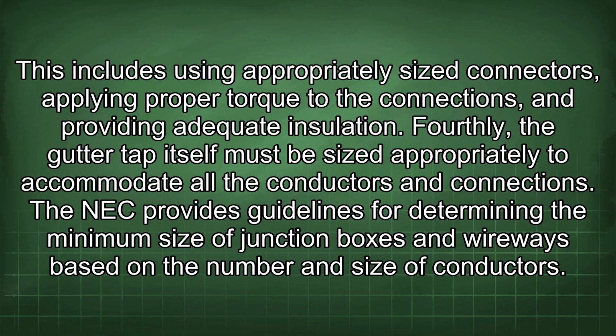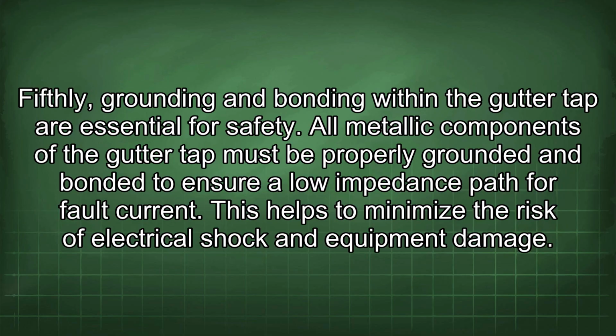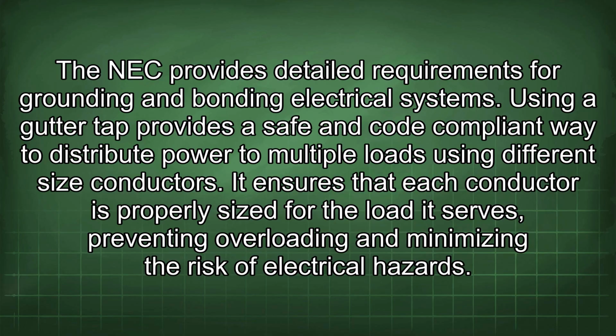Fourthly, the gutter tap itself must be sized appropriately to accommodate all the conductors and connections. The NEC provides guidelines for determining the minimum size of junction boxes and wireways based on the number and size of conductors. Fifthly, grounding and bonding within the gutter tap are essential for safety. All metallic components of the gutter tap must be properly grounded and bonded to ensure a low impedance path for fault current. This helps to minimize the risk of electrical shock and equipment damage. The NEC provides detailed requirements for grounding and bonding electrical systems.